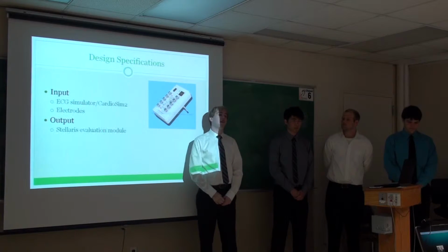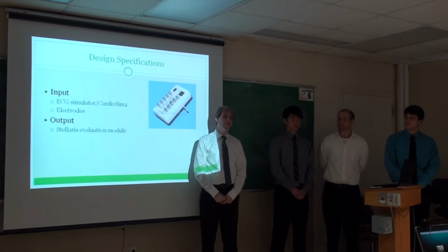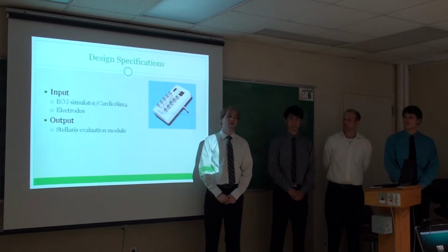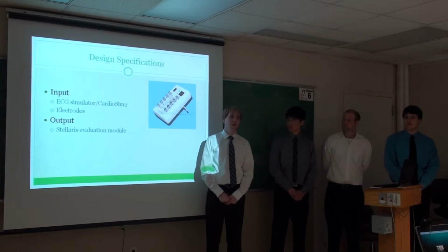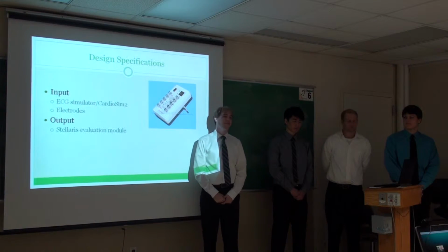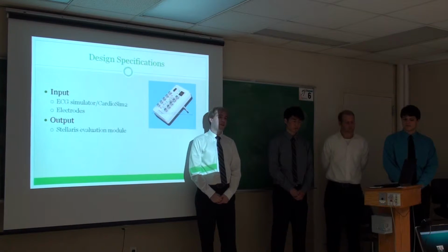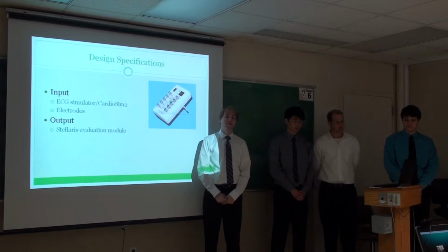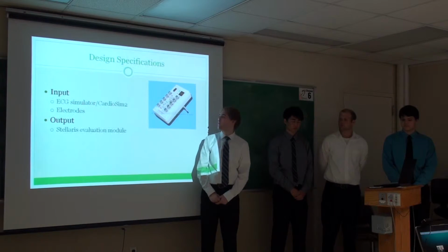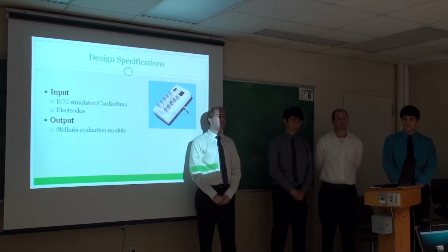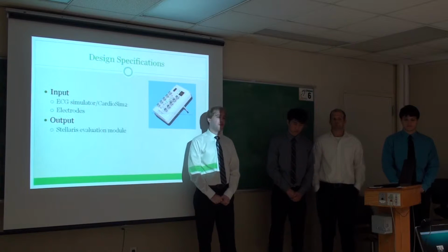And the idea behind CardioSim 2 is that it can generate 11 different types of arrhythmias. This includes your standard resting heart rate, but it also includes anything from irregular or premature atrial contractions, which are different problems that the heart can actually incur and that would be tested in a real life scenario. Now, the idea behind the project is to eventually move away from using that and use electrodes or actual test pads as our inputs, but that will be talked about more when we get to our enhancements for our project.